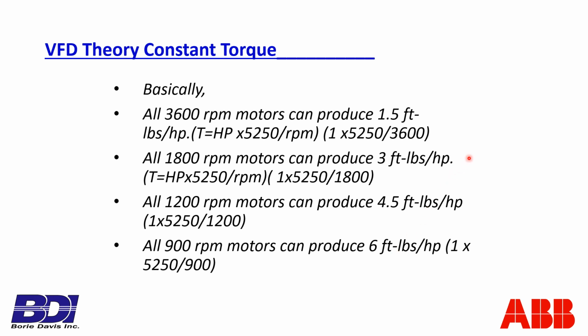And the fact is, most applications utilize a base speed 1800 RPM motor. So most applications are calculated based on 3 foot-pounds per horsepower. That would mean a 1 horse motor would be 3 foot-pounds capable, whereas a 10 horse motor would be 30 foot-pounds. And a 100 horsepower motor would be 300 foot-pounds of torque available at the shaft of the motor. That's all this is saying.